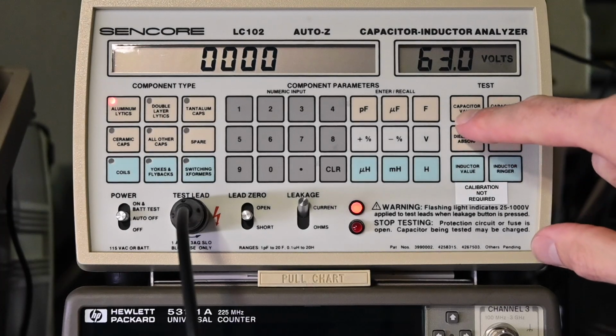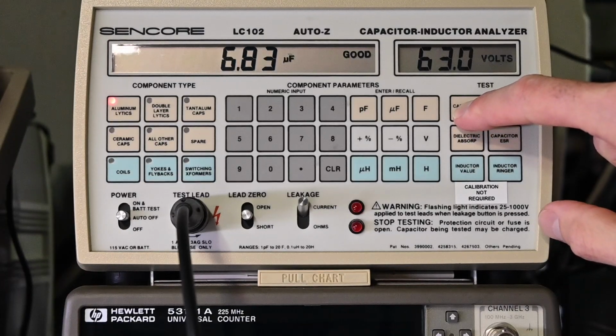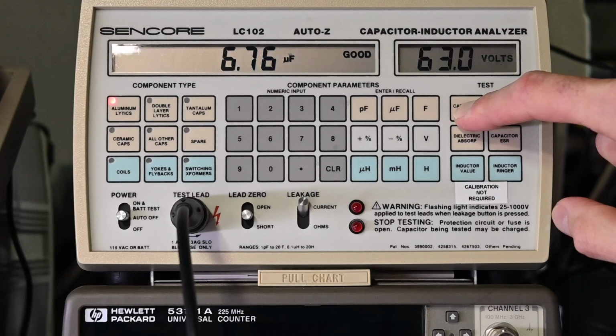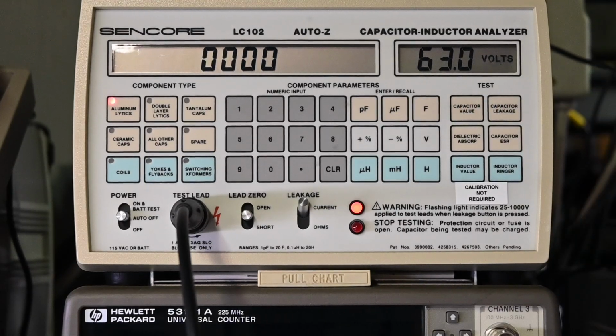So if I do the capacitance value test right here, 6.83, 6.84, so really spot on, no problems there. It does say good. So just going by the value of capacitance, you would say, oh, well, the capacitor is perfectly fine. And we already saw that with the other meters. They were all indicating a value that was very, very close to the rated value.